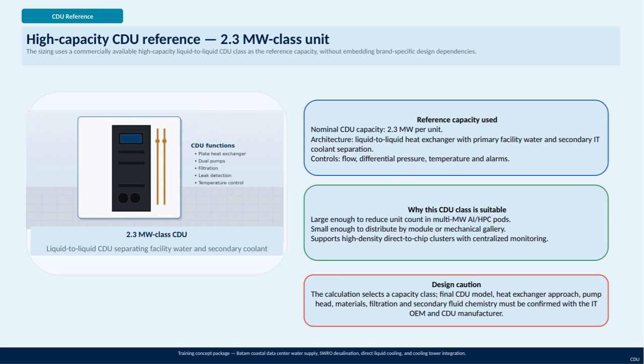The CDU itself is a liquid-to-liquid heat exchanger, which effectively separates the facility water from the secondary coolant that circulates through the IT equipment. The nominal capacity is 2.3 megawatts per unit, making it large enough to reduce the total number of units needed in multi-megawatt AI or high-performance computing pods, yet still compact enough to be distributed modularly or to mechanical galleries.